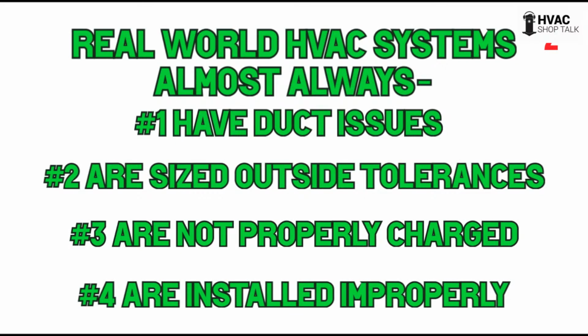So 10%, either way, it's kind of hard to find that in the field. 50%, more like it sometimes. Real world HVAC systems almost always are not properly charged. Very rarely did I see a system that I went to service and it had a perfect charge. It may have been close, and there were some I didn't have to touch because there are tolerances for that too. Let's say you were working on a TXV system that called for 9 degrees of subcooling, and that TXV would produce 12 degrees of superheat at the outdoor unit, which usually means it was at 10 degrees at the evaporator exit. Talking about a split system here.